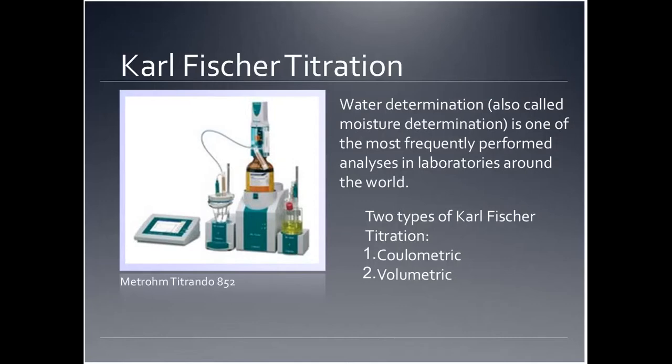Another great analytical instrument in our lab is the Karl Fischer titrator. The Karl Fischer titration is a universally acknowledged method for measuring water content or moisture determination in samples including chemicals, oils, pharmaceuticals, and food. Because water can affect product quality, texture, shelf life, stability, and reactivity, it must be readily tested to ensure it will not affect the efficacy of the product. The two types of Karl Fischer titration are coulometric and volumetric — coulometric is used for samples containing a small amount of water, while volumetric is used when there is a high concentration of water. We have one Karl Fischer titrator in our lab.